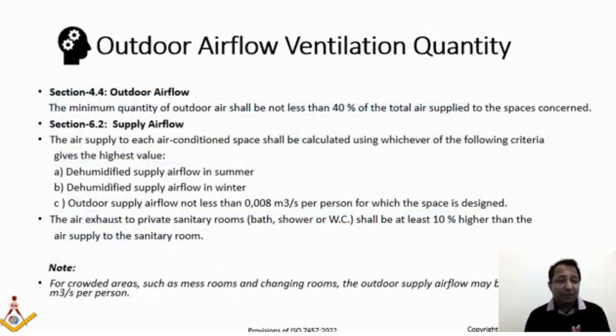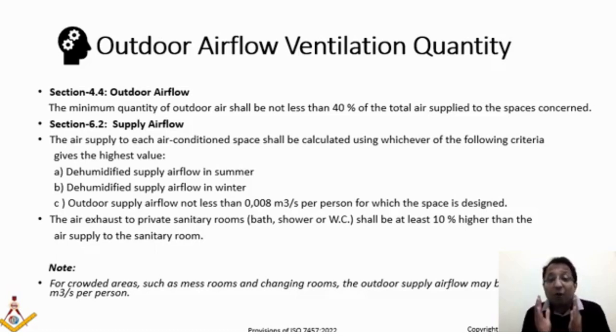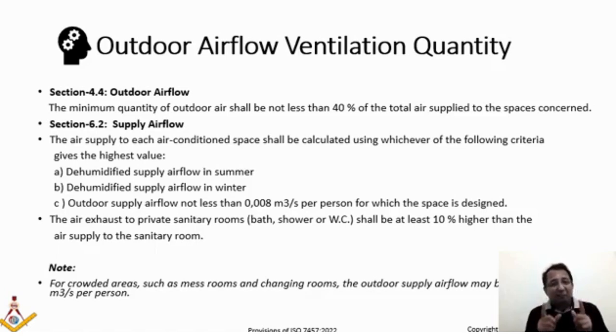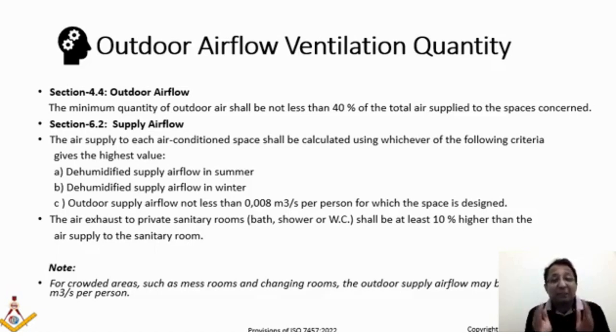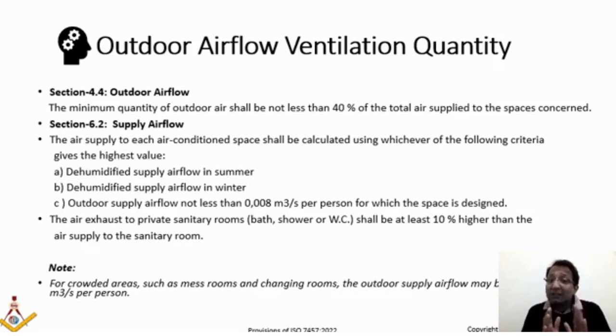Section 4.4 talks about outdoor airflow. The minimum quantity of outdoor air shall not be less than 40% of the total air supplied to the space concerned. This is an important clause — when calculating the marine air conditioning system, the outdoor air requirement must be a minimum of 40% of your total supply air. It clearly states 'shall not be less than' — not 'may not be less than.' Shall. 40%. End of story.